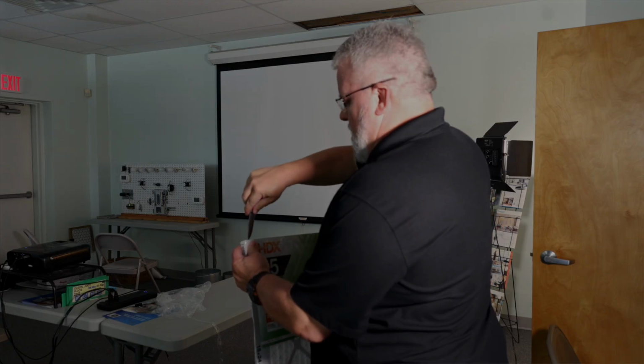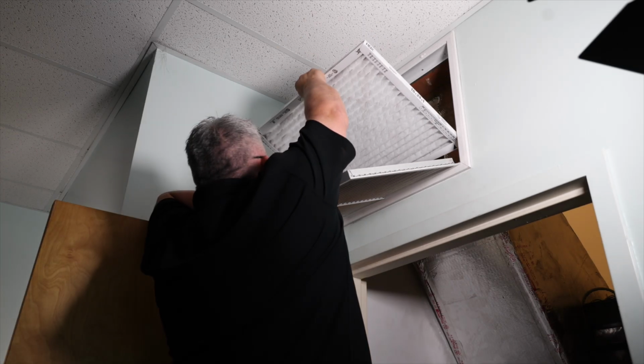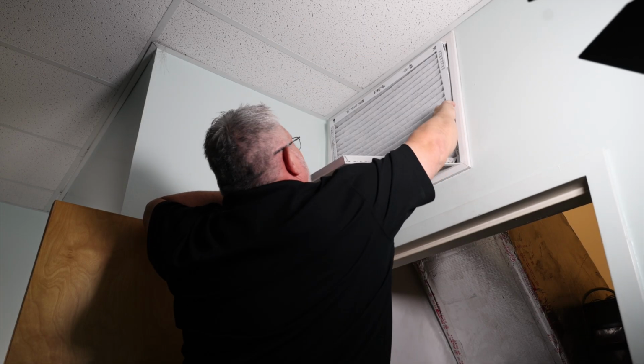This is rated as a MERV 8 filter, and interestingly enough, it actually performed better than the Filtrete 300 in terms of airflow restriction. I measured a pressure drop of 0.17 inches across this filter. Now, one thing I noticed about the HDX filters is that the filter isn't nearly as rigid as some of the higher-end Filtrete filters we'll look at later. And personally, that matters to me, because as a filter loads up with dirt and debris, over time, a flimsy filter increases the chance of air bypassing around the media instead of going through it.